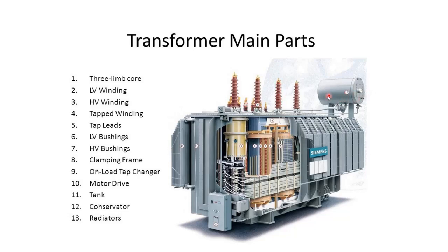From the visual you can see that this is the high voltage terminal, this is the low voltage terminal, and we have a conservator tank here, and this is an oil cooled transformer. That means inside the transformer it is filled with oil, and you have a high voltage winding and a low voltage winding mounted on the core. Surrounding the core, normally concentric high voltage and low voltage windings are placed. Now, what actually are transformer tap changers? We know from the voltage conversion of the transformer, whether it is step up or step down, that the voltage conversion is linked with the number of turns.